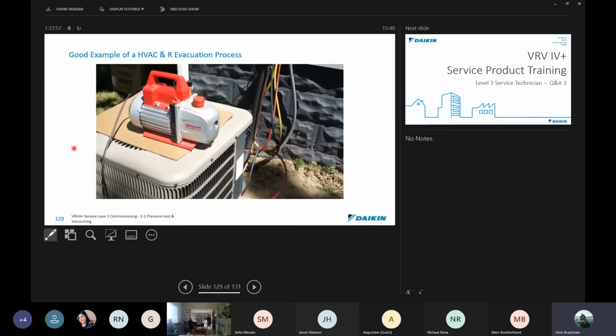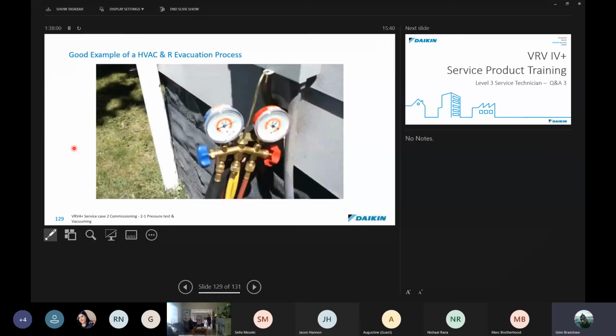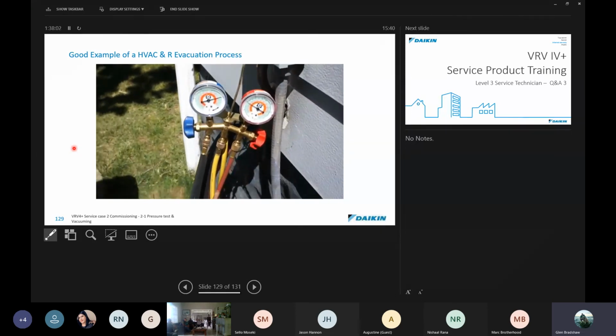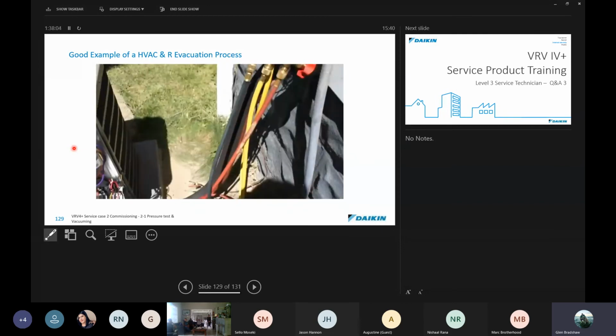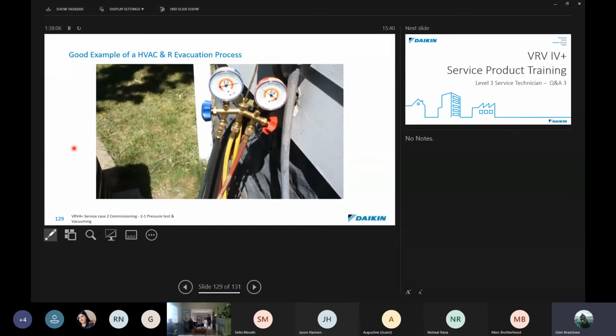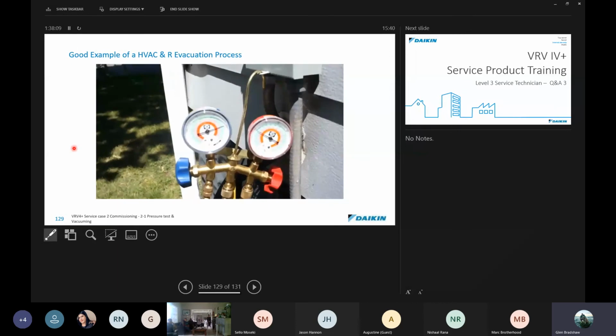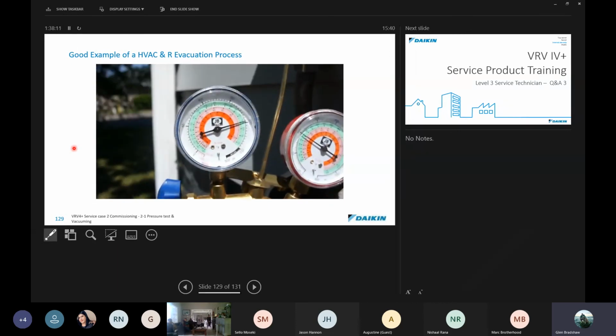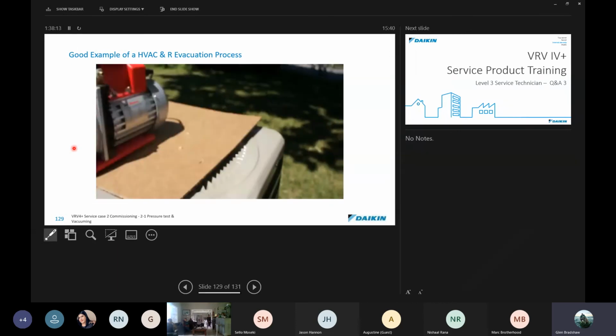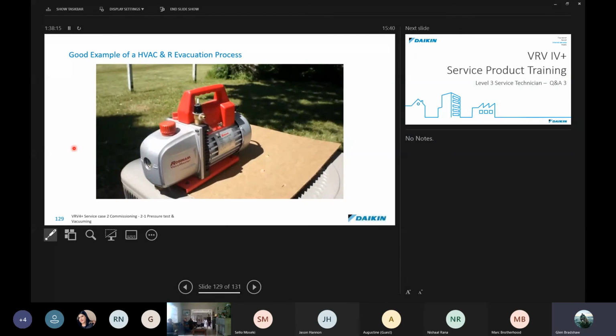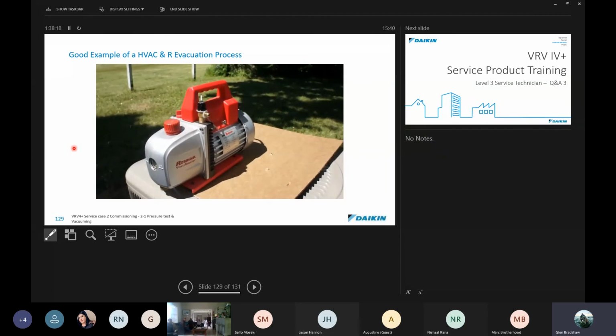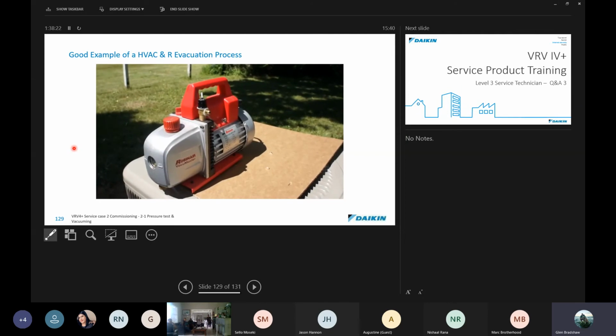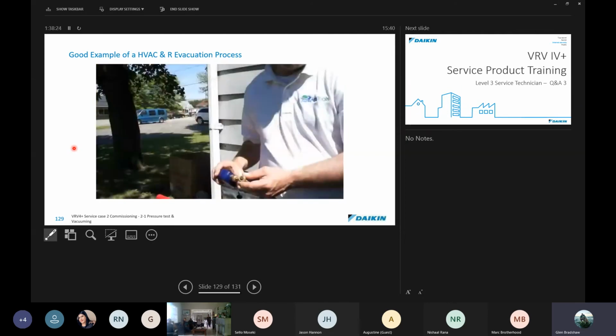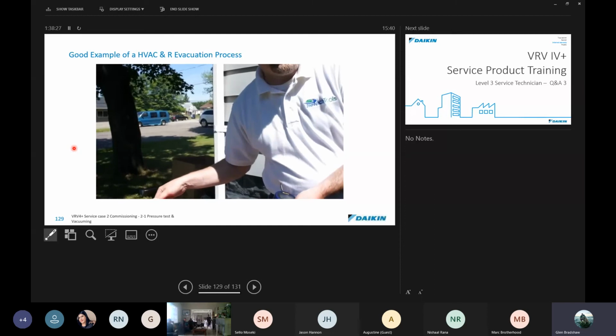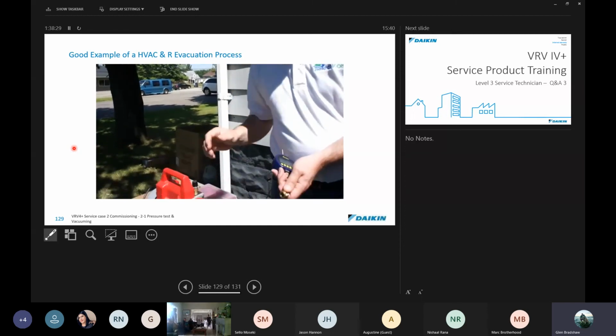So what he's got here right now is the system. These are his gauges set up, and he just did a nitrogen sweep, pushed the air out of the system, and has it on a standing pressure test at a couple hundred PSI. It's sitting here ready to roll, and we're going to hook the blue back up to his pump. We're going to test his pump first to make sure it will pull down to below 100 microns. No power yet? Let's see. There we go.